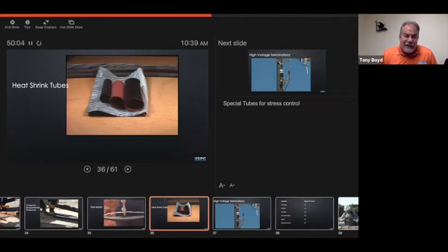There's also the heat shrink tubes. You can see the 3 different tubes. There's the one conductor tube, which provides an even roundness onto the conductor. The second one is your insulation layer. It actually works exactly like the insulation that's on the cable itself. And then the outer is a semiconductor, and then you would have some other kind of sealant or something on top of that one.